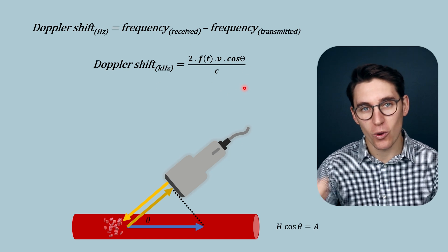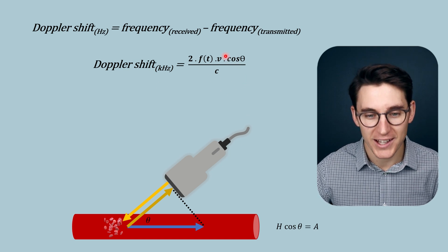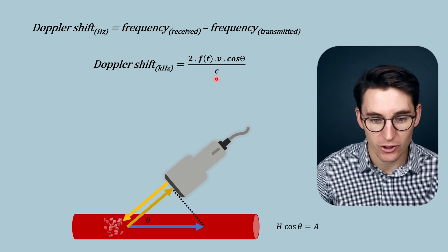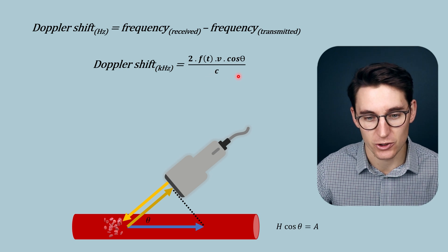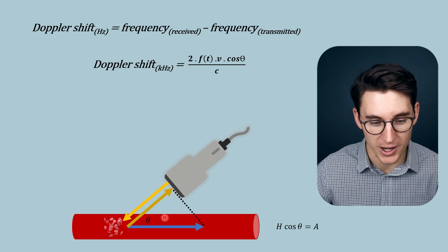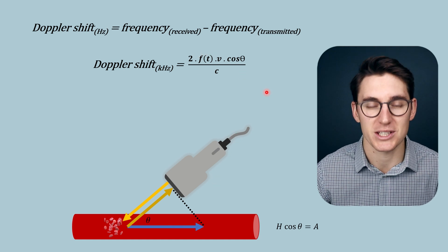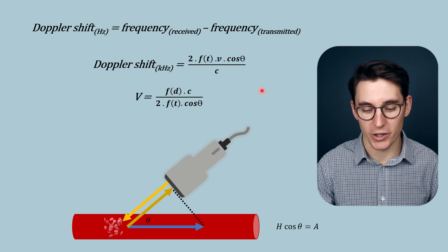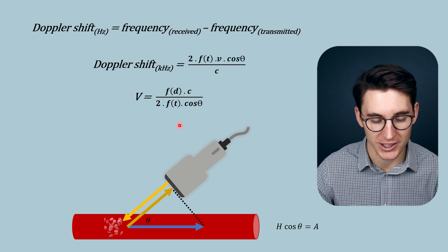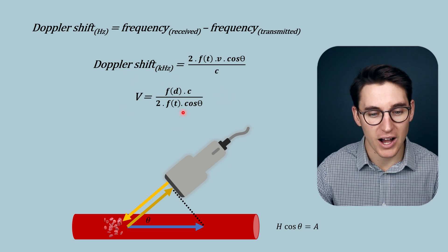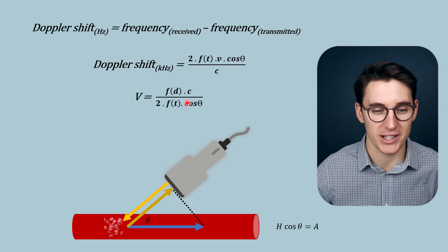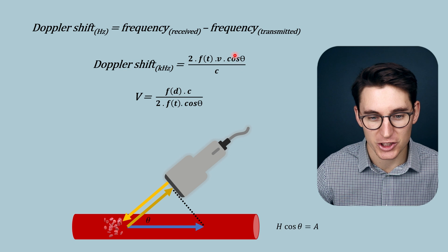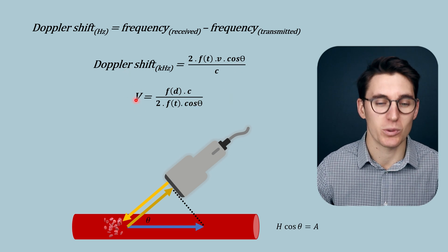What we are trying to calculate in Doppler ultrasound is the velocity — this is our unknown. The machine calculates the Doppler shift; we know the speed of sound within tissue, the angle of incidence programmed into our ultrasound image, and the frequency of our transducer. We rearrange this equation to have velocity as the variable. In exams, you likely won't be asked to calculate the velocity of blood flow, but you need to understand the relationships between these variables and the Doppler shift as well as velocity.